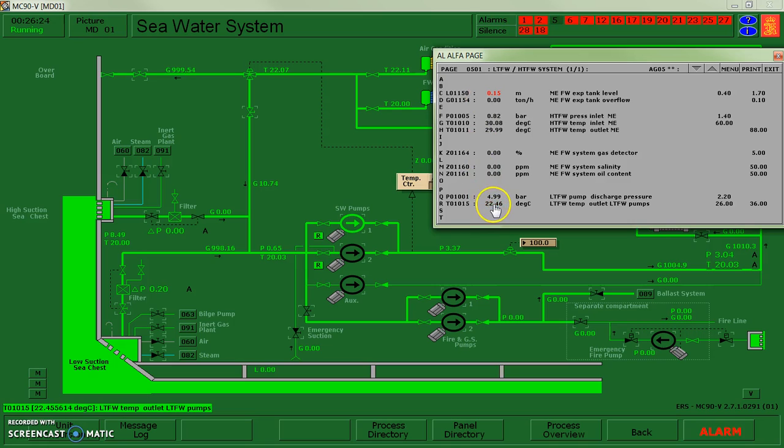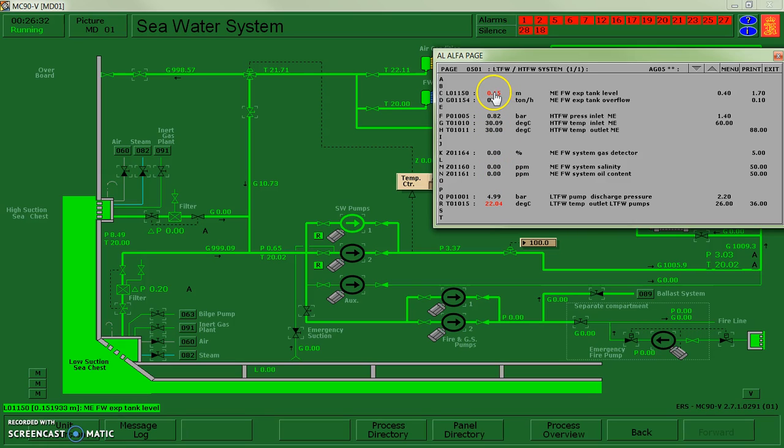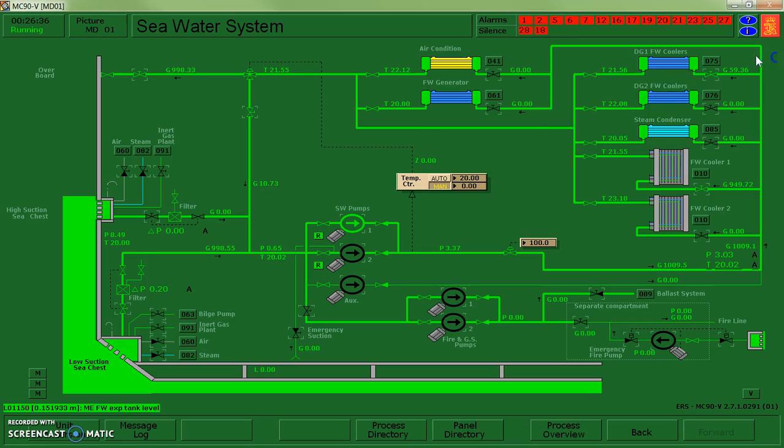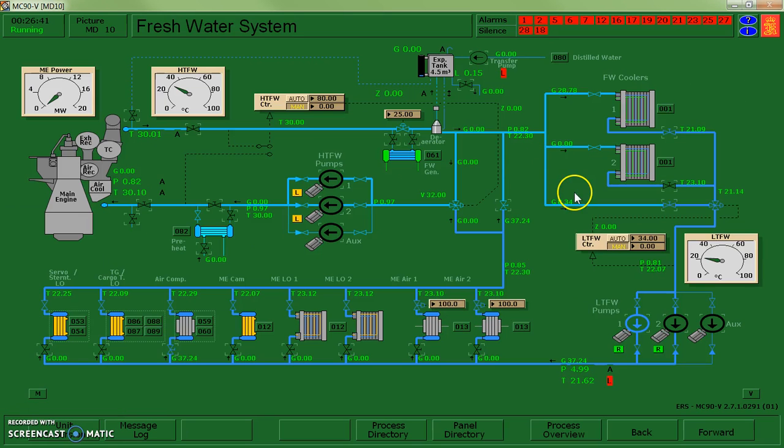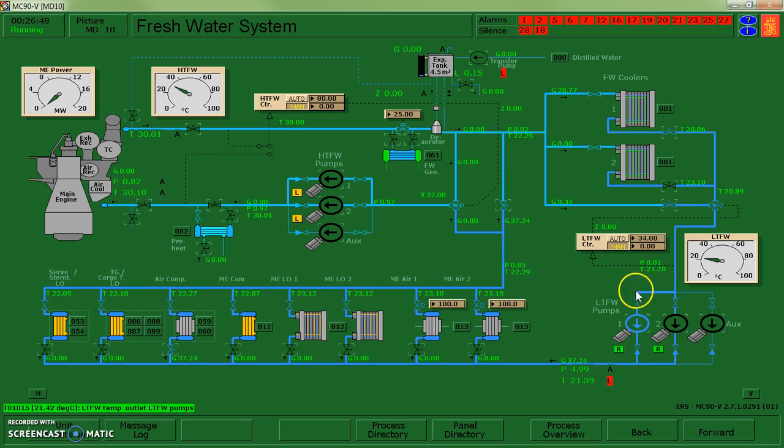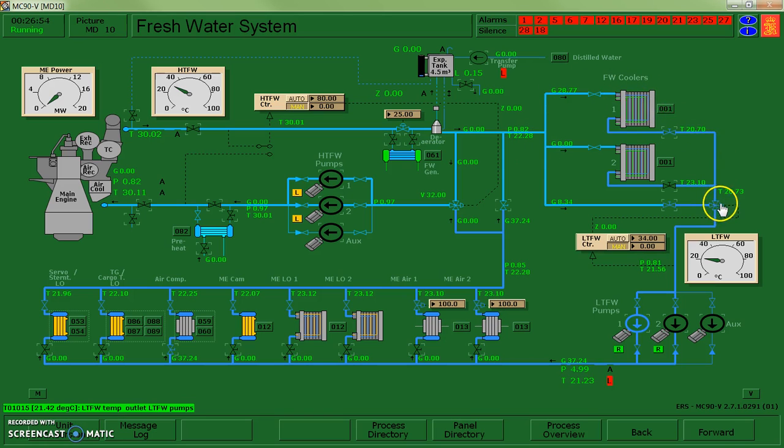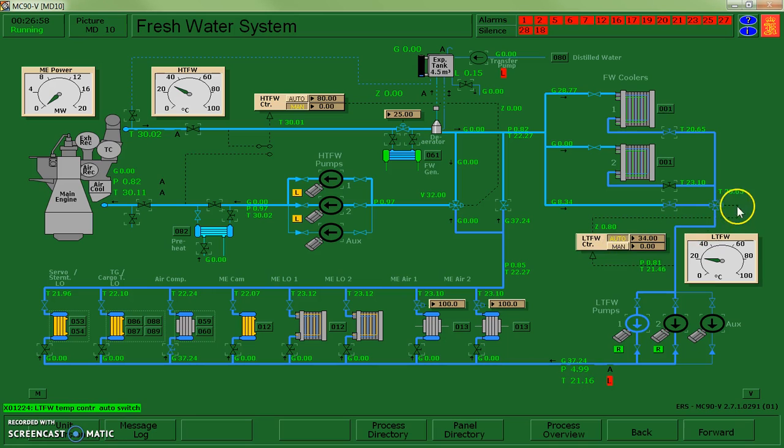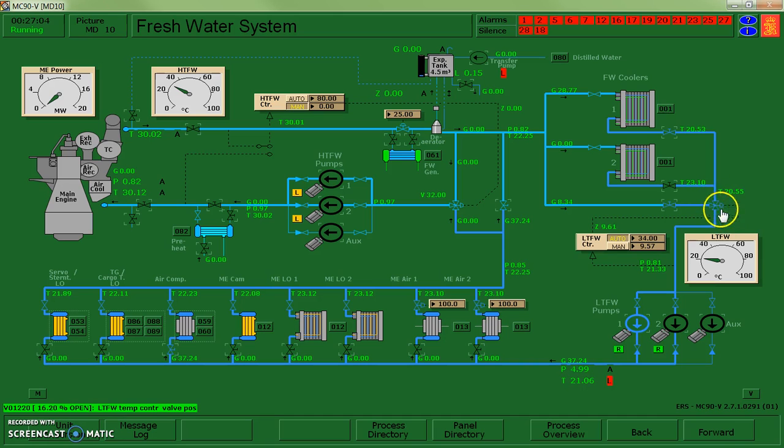Again, as we're starting up a lot of these systems wake up and I don't have levels where I need to be. This guy's issue was that he was too cold. Right now I'm sending most of my cooling water through the cooling pathway. I'll set this to auto and eventually it'll fix itself. However, I don't have any control air so this valve is actually dead at this point.